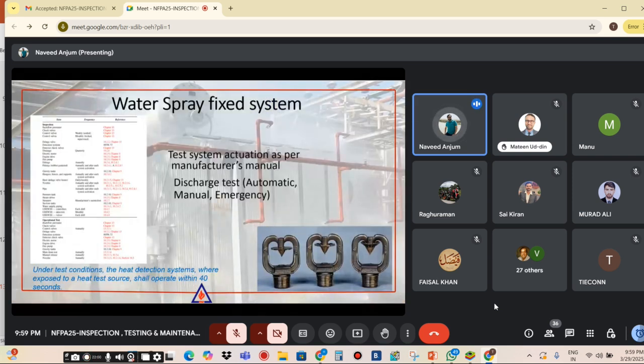Then one person also said that they are performing a water spray fixed system, and there are tables in NFPA 25. Each table first tells you about inspection, then testing, operational testing, and then on the next page it shows maintenance, and it also mentions references, in which chapter, for which system. If there is a detection system, then it refers to NFPA 72. So you have to check the test of system actuation as per the manufacturer manual, and discharge tests, automatic, manual and emergency, and the different steps you have to check.